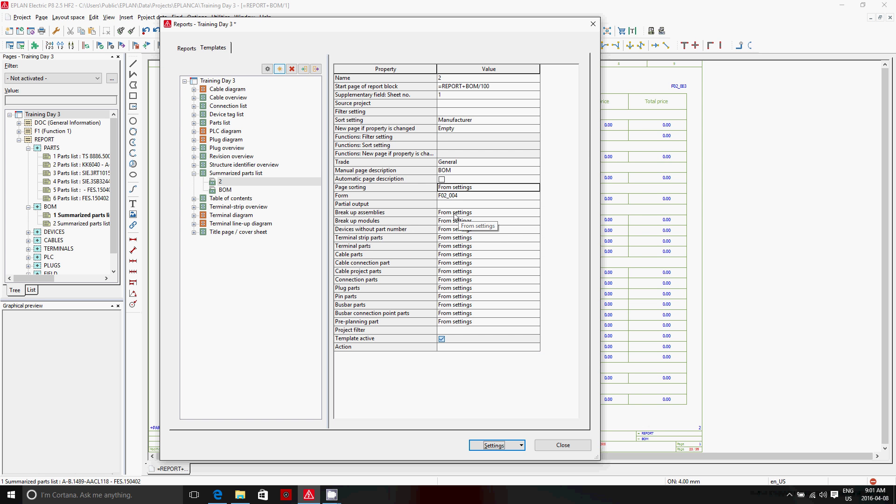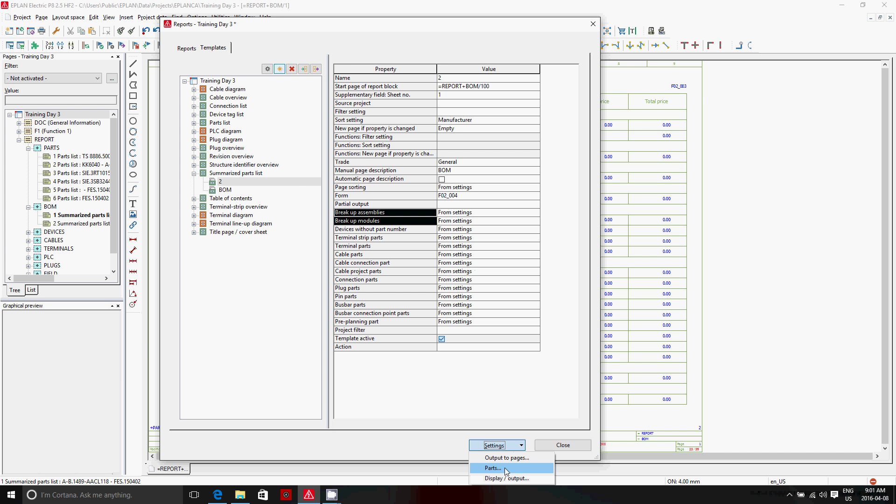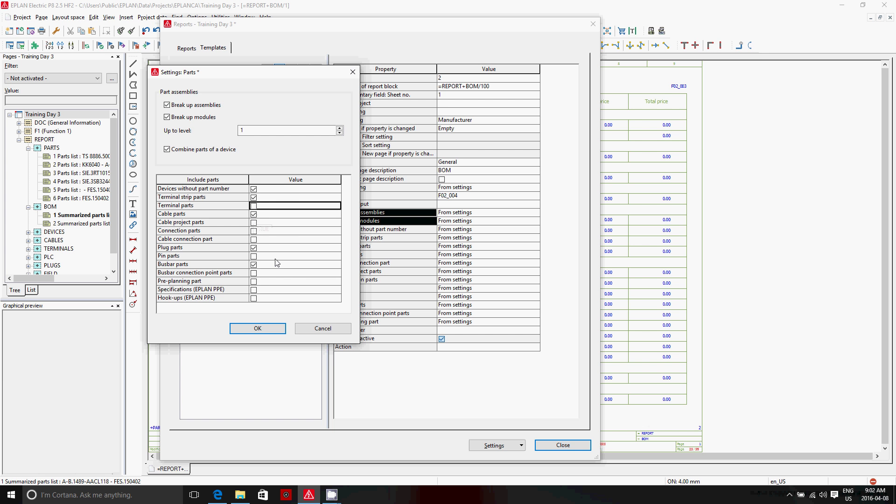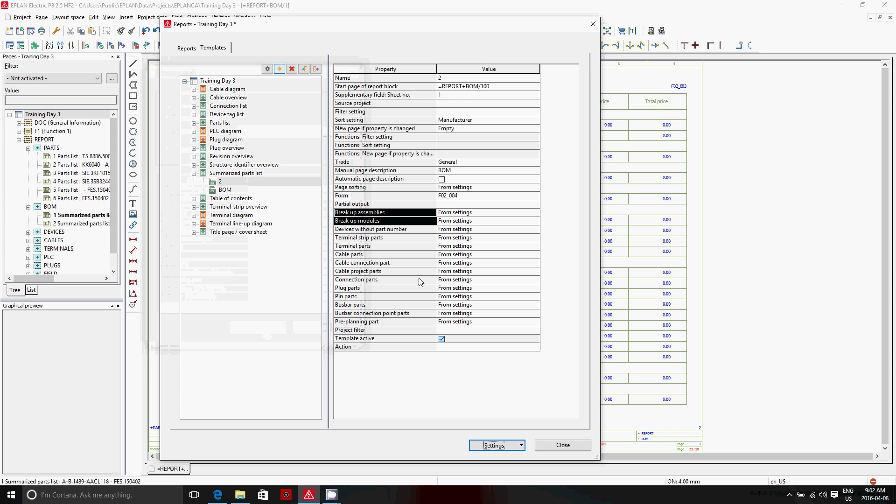Then further down, because we are handling parts, we have a question about breaking up assemblies. Breaking up assemblies, the default settings are here, is basically going to break up an assembly like a fuse holder with a fuse and a cap that are assigned with one part number, but represent three part numbers. If you click here, break up assemblies, it's going to break them up. The other thing you can do here is you can specify what type of parts you want. So you could actually specify that you don't want the terminals, or you do want the terminals to show up. Because they may be ordered per project, or they may be ordered more as general from the electrician, so you don't have to handle them per project. It's up to you.